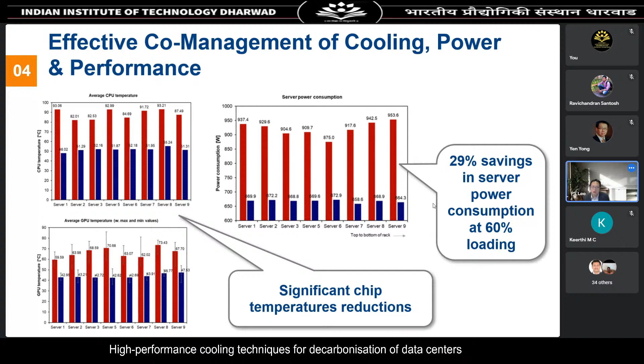Once you're able to greatly lower your chip operating temperature, or chip junction temperature, your server power consumption or chip power consumption drops very substantially. At 60% loading, we recorded a 29% reduction in server power. So besides the savings from your cooling system, you get this additional side benefit of significant IT power consumption reduction. Those are the two advantages of switching from conventional air cooling to high performance liquid cooling. And that's not all.